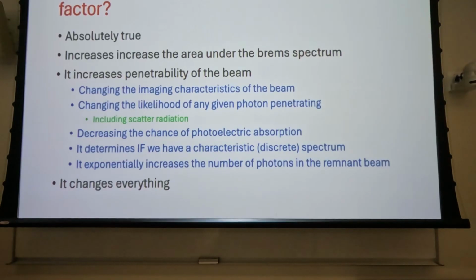Quality, beam quality. But in the patient, what does it control? Penetration, right. So if you increase your kVp, you increase quality of the X-ray beam, and we equate kVp to quality because if you shoot with an X-ray beam so low it doesn't penetrate the patient, what good is it for us? What are we trying to do? Get a good picture. Penetrate the patient so that we can see the interior contents, what the patient's got in them, and make a diagnosis. So if we don't penetrate the patient, it has no quality, right? So the higher the kVp, the higher the beam quality. Doesn't necessarily equate to image receptor quality or image quality, but it does directly affect the beam quality. All right, so it increases penetrability of the beam. The higher the kVp, the more you can penetrate. Changing the imaging characteristics of the beam.